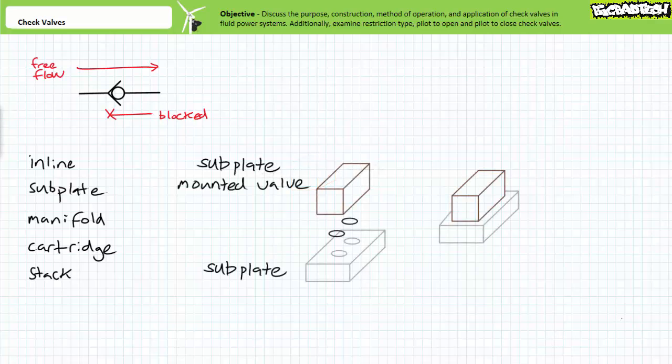In contrast, a subplate mounted valve uses a machined subplate directly attached to system plumbing, and the valve is then attached to the subplate with threaded connections. O-rings and/or gaskets prevent leaks between the matching valve and subplate ports. Standardized size of subplates and valves allow quick interchangeability.